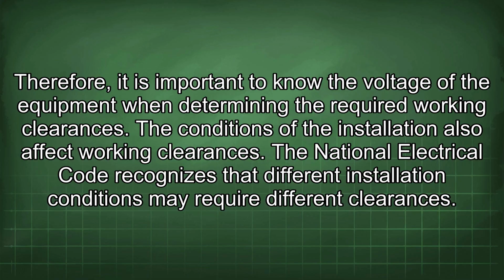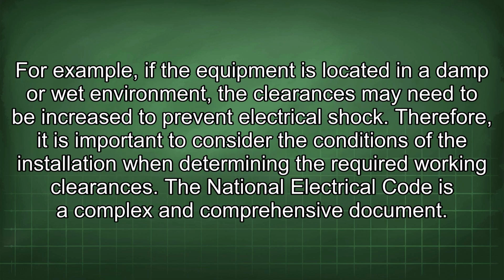The conditions of the installation also affect working clearances. The National Electrical Code recognizes that different installation conditions may require different clearances. For example, if the equipment is located in a damp or wet environment, the clearances may need to be increased to prevent electrical shock. Therefore, it is important to consider the conditions of the installation when determining the required working clearances.